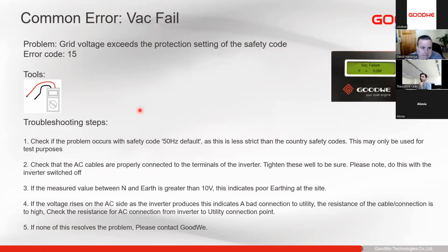VAC fail is very similar to utility fail, but it is a voltage error. So we're saying the voltage is incorrect. Sometimes you'll see this when the grid is off as well. You'll see VAC failure. But if the voltage is out of operating range, we will also get the VAC failure. So we can change the country safety code to 50 Hertz default, which is a wider input code. It's less strict than most safety countries. And then we use this for test purposes.